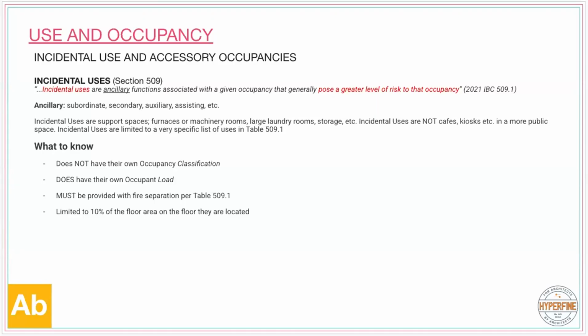Incidental use must be provided with fire separation. There's a table 509.1. And actually, I forgot to mention that this table 509.1 lists the only things that are allowed to be incidental uses. It's 15 or 20 long. And it's limited to 10% of the floor area on the floor they're located. So you might have that number memorized.